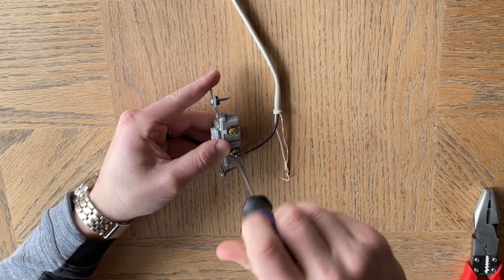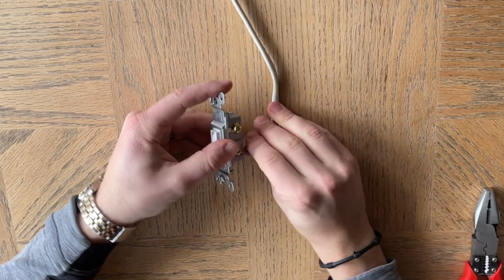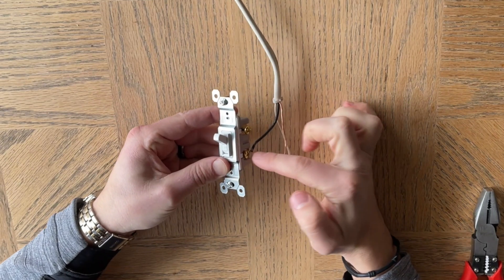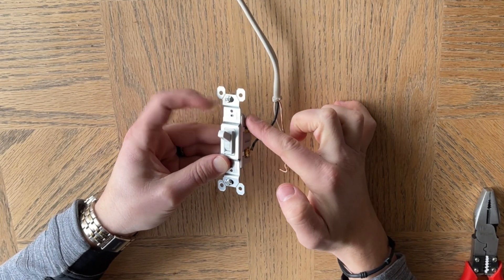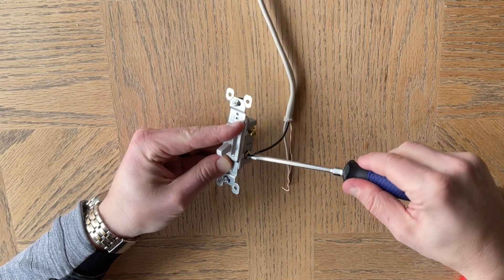Now why do we put the live on the bottom? Because a switch is an interrupter. So when you turn it on, it would be turning up and then taking the power from the bottom terminal up to the top terminal and continuing that circuit flow. When it's off, it's breaking the circuit.